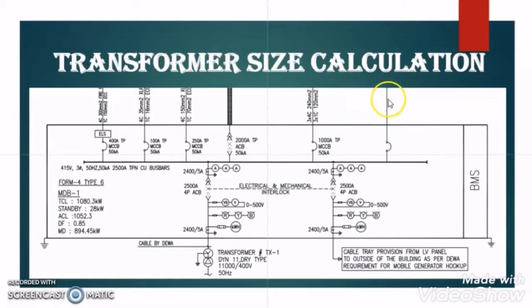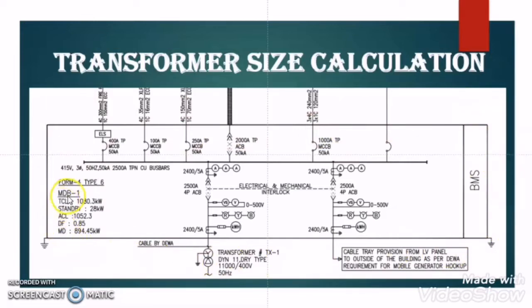The part 1 video was the conceptual video and in this video, we will take an example and based on the example, we will try to size the transformer. Here I took one SLD and from that SLD, this is the MDB panel — MDB 1. The total connected load on this MDB is 1080.3 kW. The standby load connected with this MDB is 28 kW and the actual connected load is total connected load minus standby load, that is 1052.3 kW.